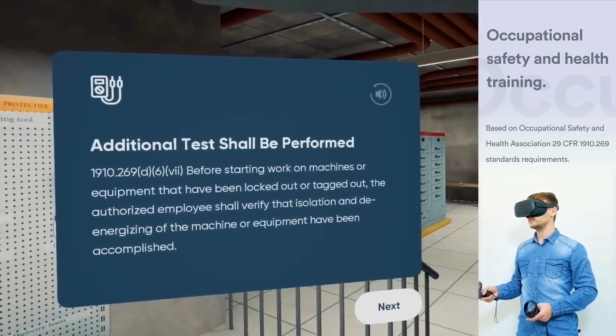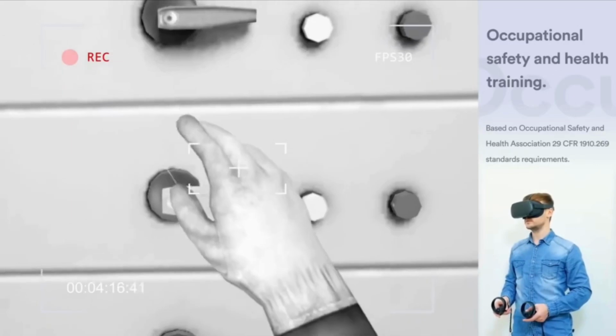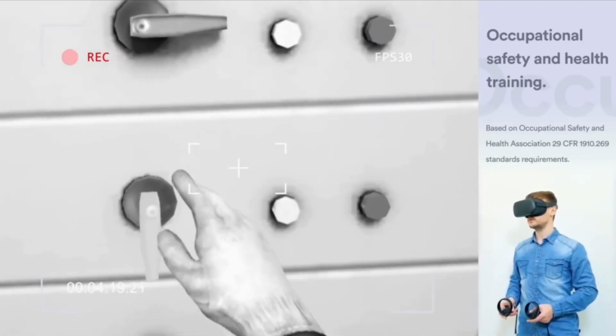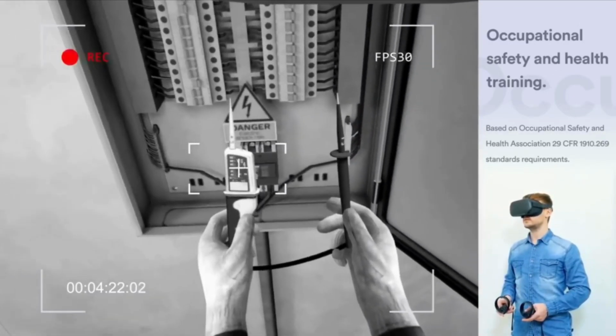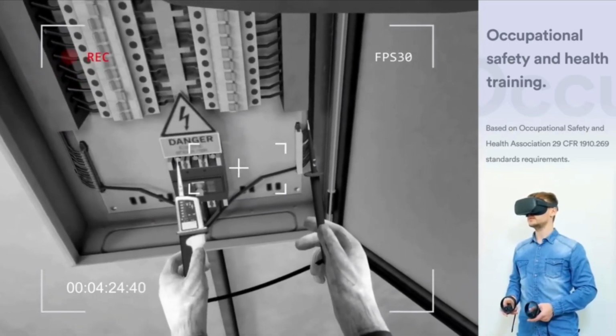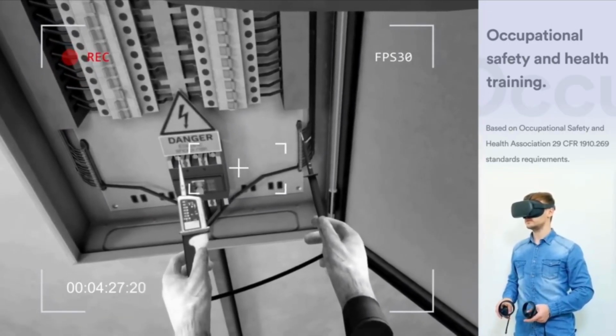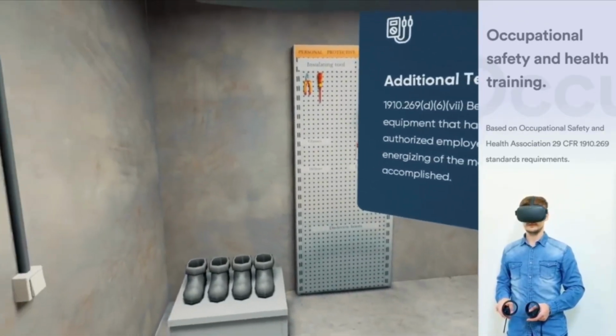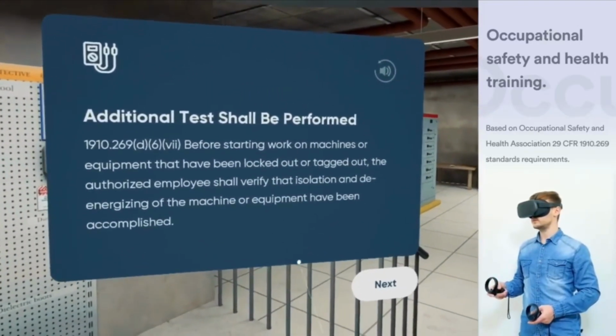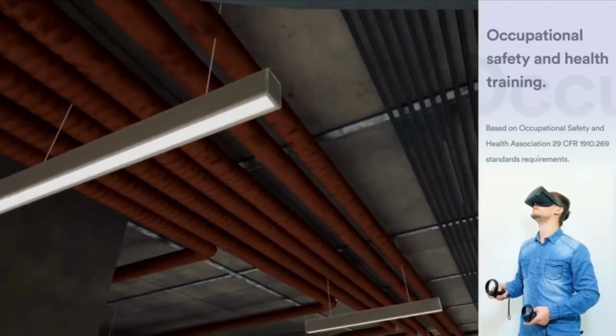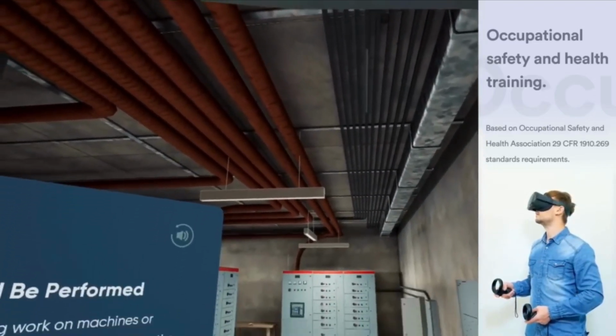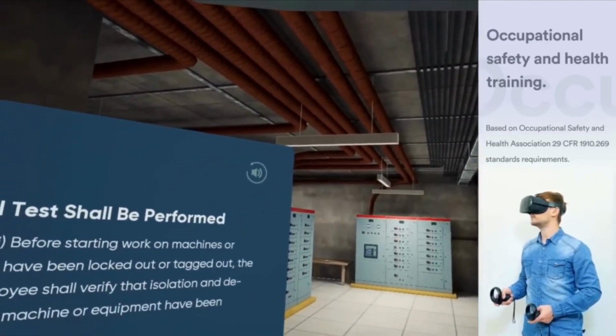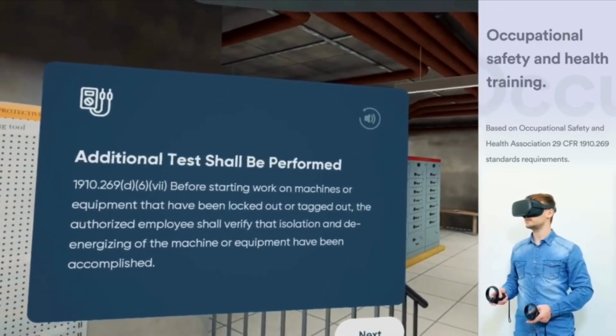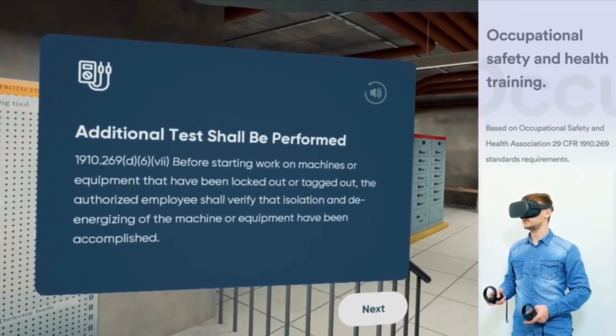The additional test shall be performed. After switching off the circuit breaker on the switchboard panel 3, an additional test shall be performed to verify that isolation and de-energizing of the panel 1 were accomplished. According to the OSHA standards, before starting work on machines or equipment that have been locked out or tagged out, the authorized employee shall verify that isolation and de-energizing of the machine or equipment have been accomplished. If normally energized parts are exposed to contact by an employee while the machine or equipment is de-energized, a test shall be performed to ensure that these parts are de-energized.